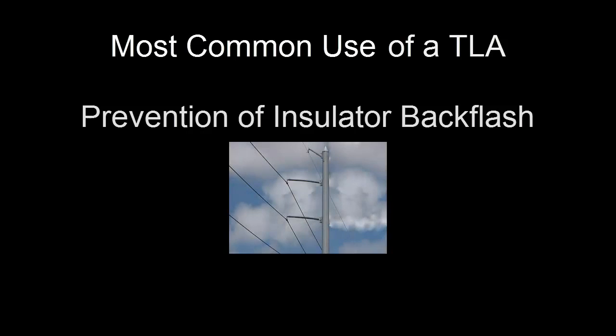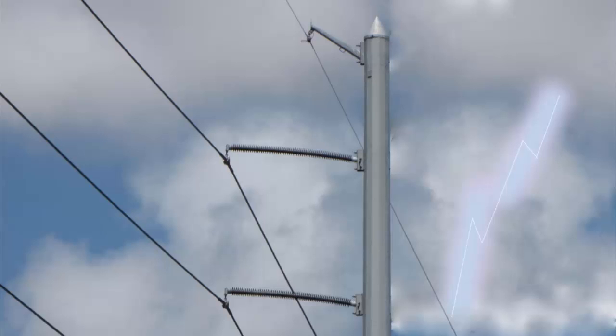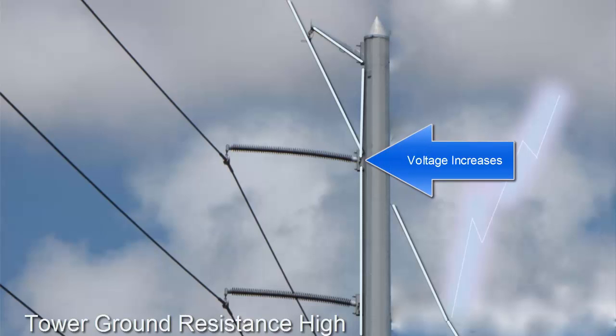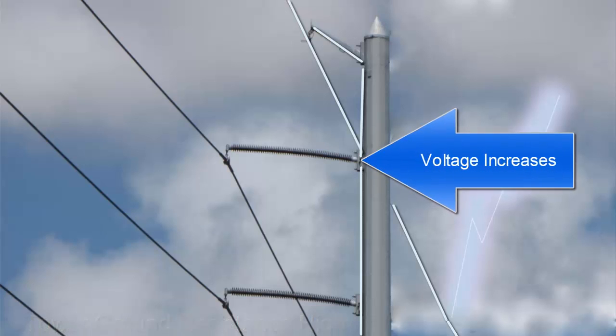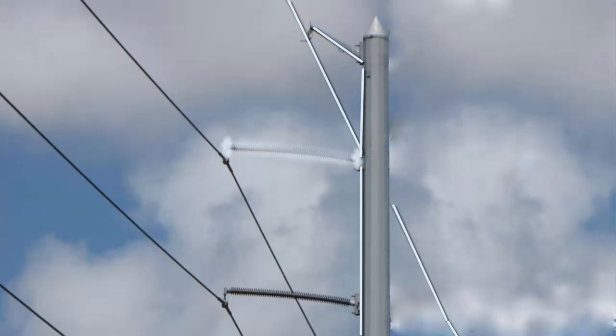The most common use of the TLA is the prevention of insulator backflash on shielded transmission lines. In this graphic you see how the backflash is created during a strike. When the overhead ground wire intercepts a lightning stroke, it conducts the current to ground via its downground. If the tower ground resistance is too high, the voltage at the base of the phase insulator will increase.